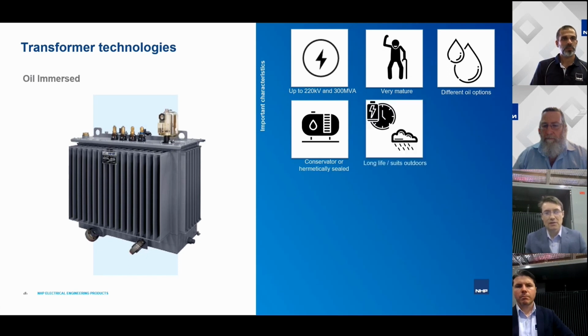So the advantage of such a transformer over the conservator type is that the oil deteriorates much slower because it's not in contact with oxygen. The larger power transformers, though, have to be conservator type, where you have an additional conservator, which is an additional tank that allows oil to expand and contract depending on the temperature of the transformer. This is where the oil level goes up and down, but the oil is in contact with air in that case. So it's not possible to do otherwise for these larger transformers. So there are more specific requirements for more frequent testing and more protections.